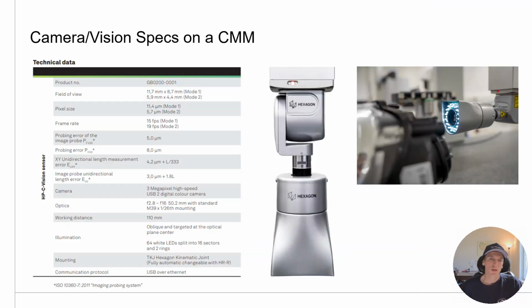So I'll finish up here with the specifications of these. This is for the Hexagon camera, and I cannot stress this enough. This is the camera that goes on a bridge CMM, not a primary vision machine that might also have a tactile sensor. So the camera systems that you might add on after the fact or later on onto a CMM are going to have an accuracy of about 8 microns or about 5 microns for probe error of the imaging or of the image. And in general, you saw how fast they move. They whip around a part, but they really are well suited for those 2D measurements.